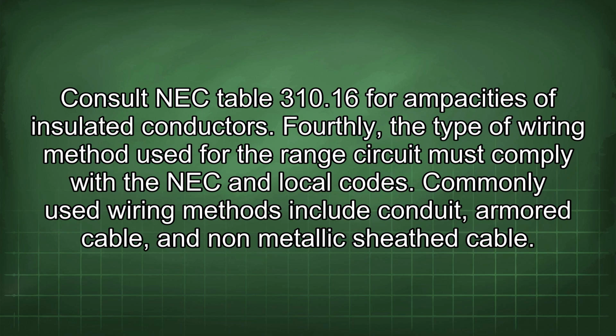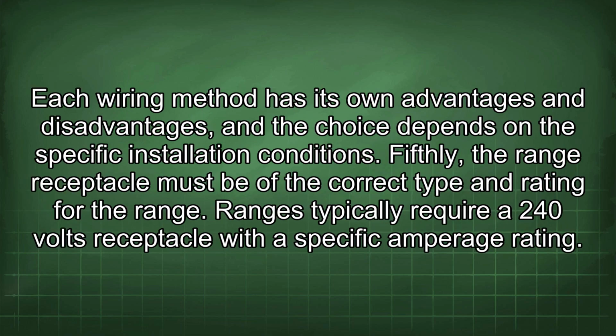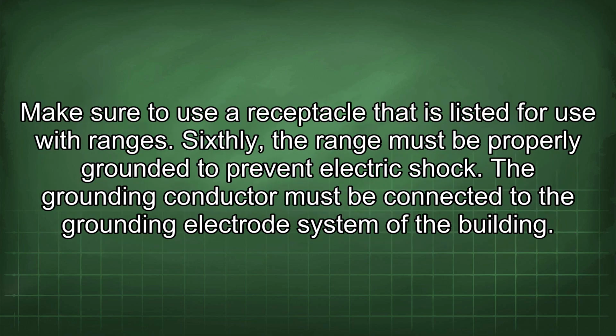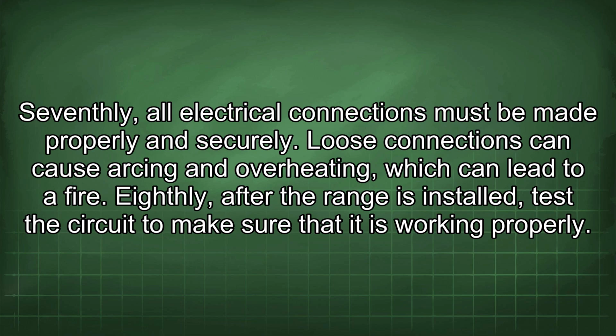Fourthly, the type of wiring method used for the range circuit must comply with the NEC and local codes. Commonly used wiring methods include conduit, armored cable, and non-metallic sheath cable. Each wiring method has its own advantages and disadvantages, and the choice depends on the specific installation conditions. Fifthly, the range receptacle must be of the correct type and rating for the range. Ranges typically require a 240 volt receptacle with a specific amperage rating. Make sure to use a receptacle that is listed for use with ranges. Sixthly, the range must be properly grounded to prevent electric shock. The grounding conductor must be connected to the grounding electrode system of the building. Seventhly, all electrical connections must be made properly and securely. Loose connections can cause arcing and overheating, which can lead to a fire.